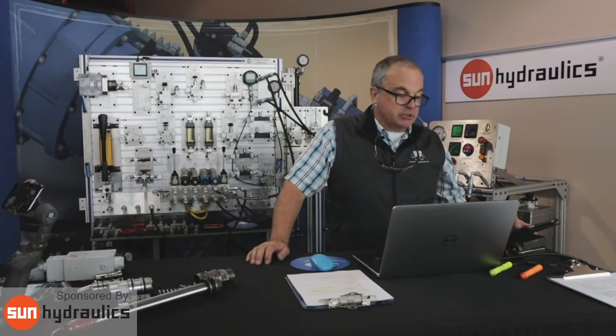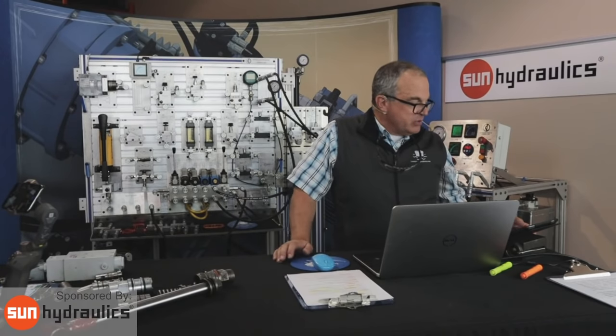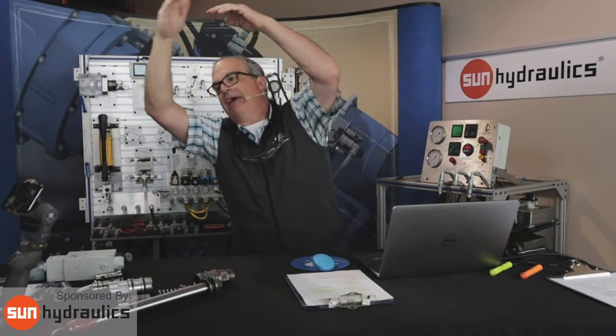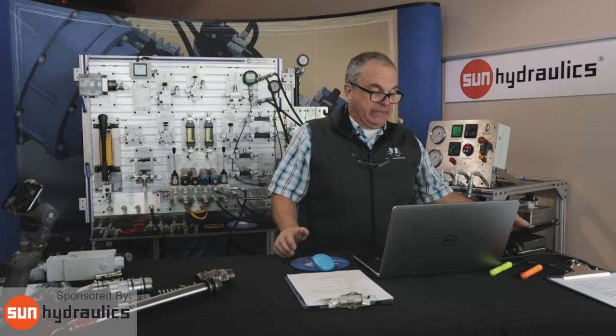All right, that's a lot of information for our short time together. Can't possibly cover off on all of the dynamics that happen in the world of load controlling, motion controlling. Concrete pumping trucks with an articulating boom with many sections. You know that carpenter's ruler that folds out in many sections like a Swiss Army knife? Wow, if you watch those concrete pumping trucks set up on site, those types of booms with many articulating sections which begin pushing one way and then by the time they're extending out are over center, very dynamic environment to try and make all of the best possible calculations for a counterbalance valve. We've shown you a system that only had a straight vertical down and we could see there was already a little bit of dynamics there.